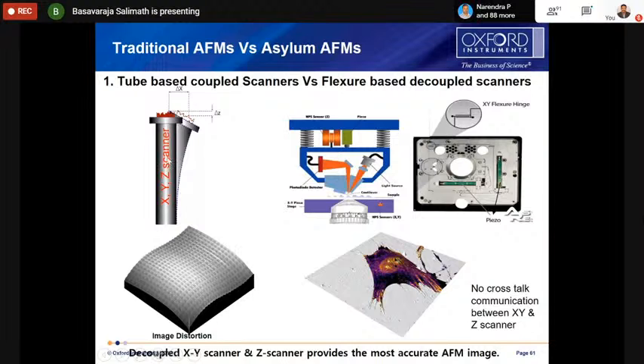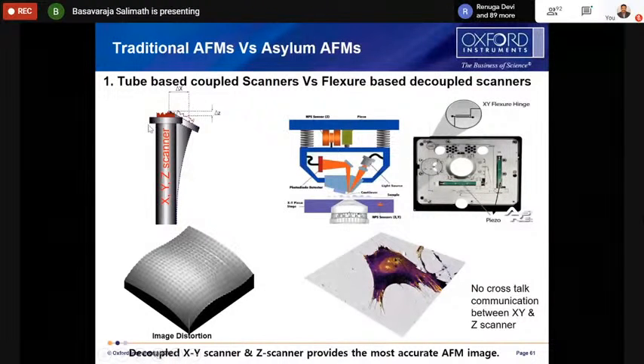Here it's a tube scanner. In a tube scanner the bottom end is fixed and the top end is moving. As one end is fixed, when it moves you get some kind of bow in the image. Whereas here, these are flexure based scanners, not tube based, so you get almost flat images. Here you can see your surface is actually flat, but you get some bow because of the scanner design. And all our AFMs have this kind of design.